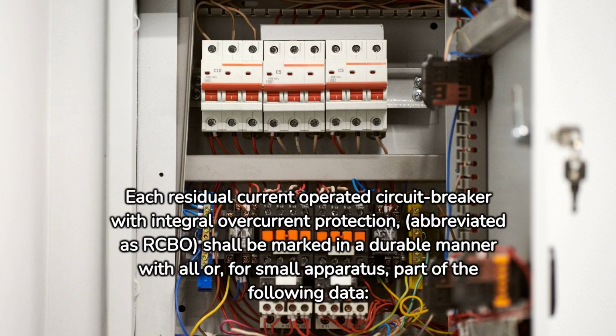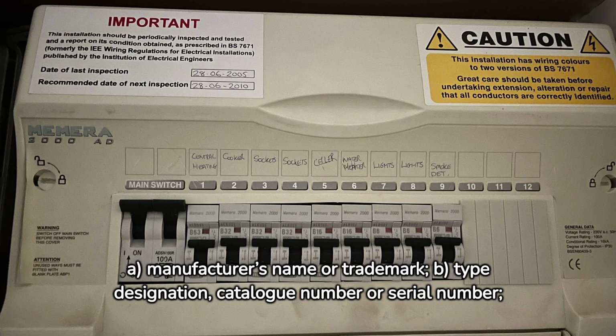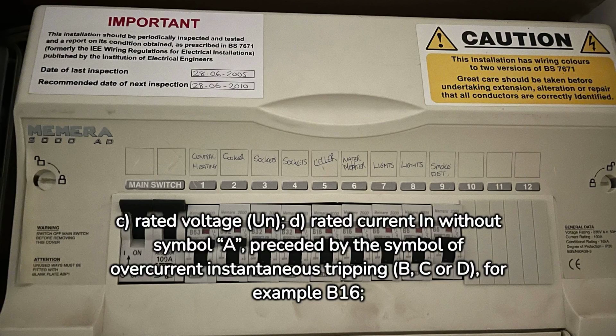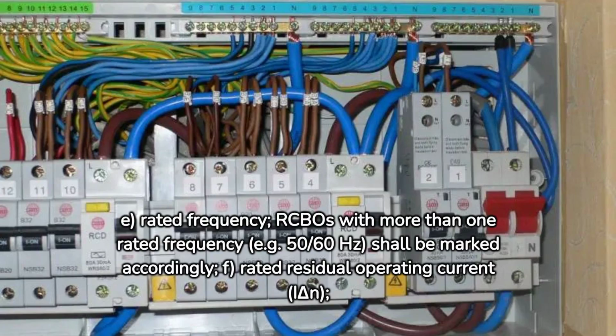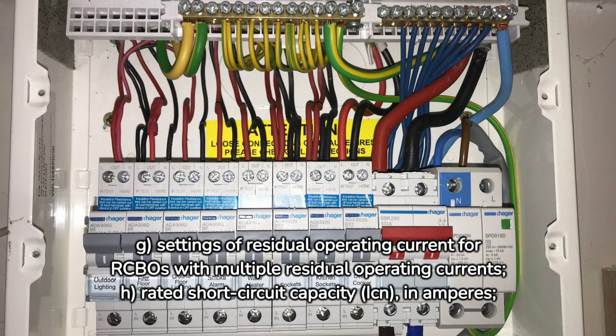Each residual current operated circuit breaker with integral overcurrent protection, abbreviated as RCBO, shall be marked in a durable manner with all or, for small apparatus, part of the following data. A. Manufacturer's name or trademark. B. Type designation, catalog number or serial number. C. Rated voltage, Un. D. Rated current, In, without the symbol A, preceded by the symbol of overcurrent instantaneous tripping, B, C or D, for example B16. E. Rated frequency; RCBOs with more than one rated frequency, e.g. 50/60 Hz, shall be marked accordingly. F. Rated residual operating current, IΔn.